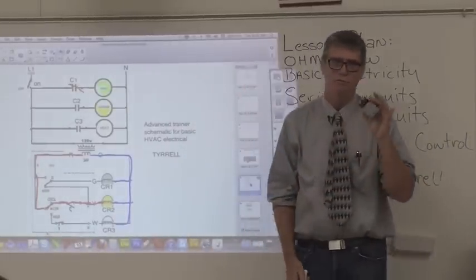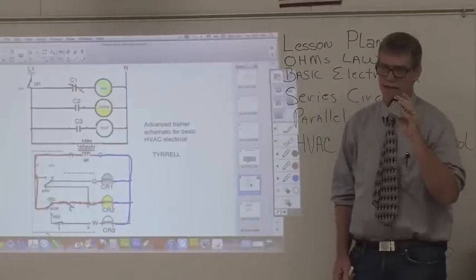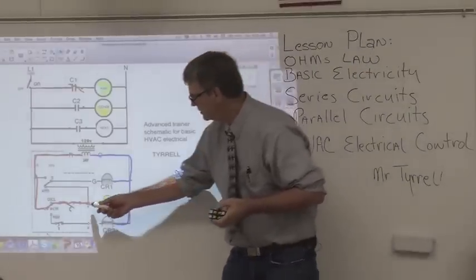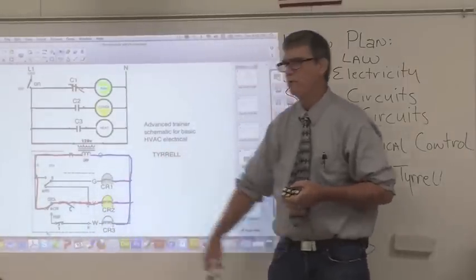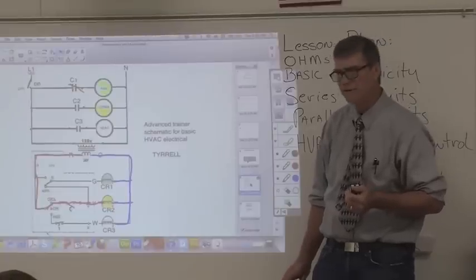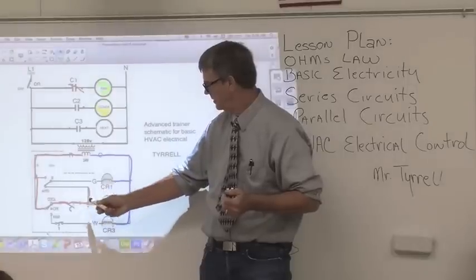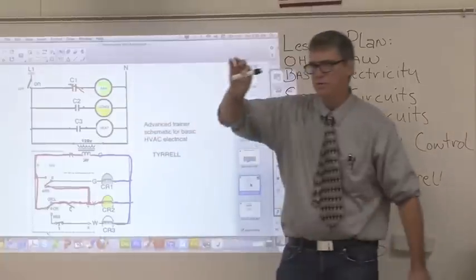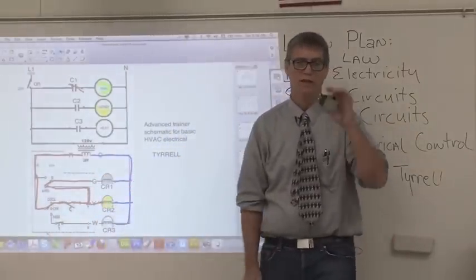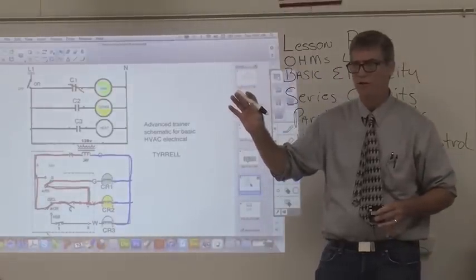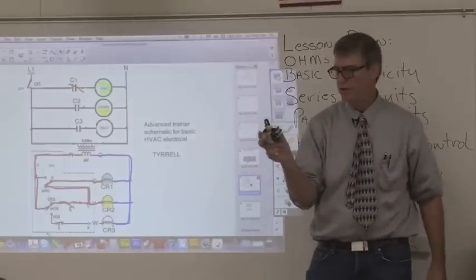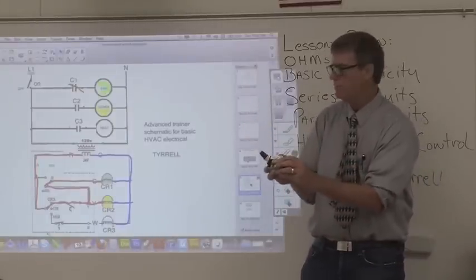What else has to start when we want to cool the house? The indoor fan motor — that would be in the furnace or air handling unit. How does this 24 volt power get to the fan motor relay? Once Y is a closed circuit, the power will automatically come up to G. If you have your thermostat switch in the auto position, that is automatically going to follow out terminal G, and terminal G is what starts that indoor fan motor.